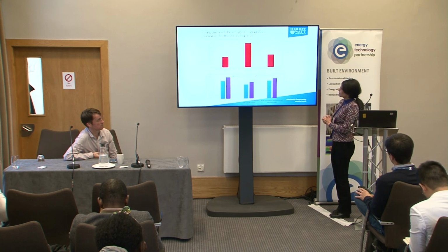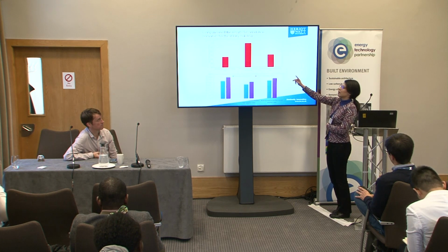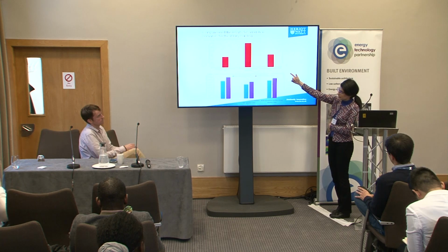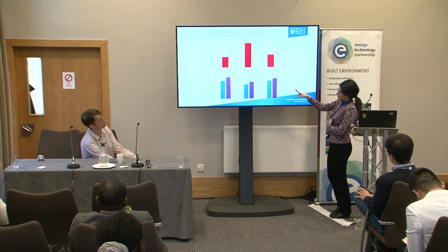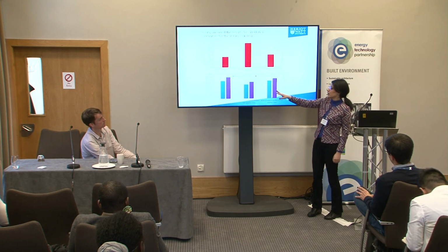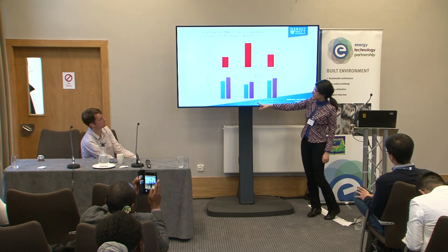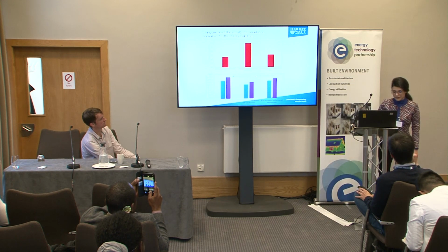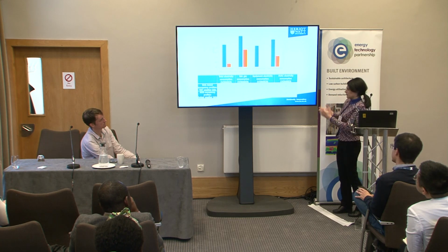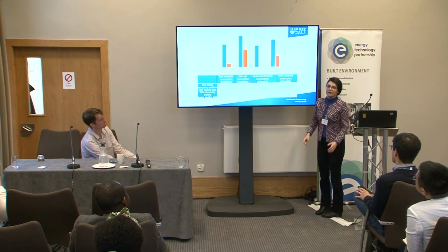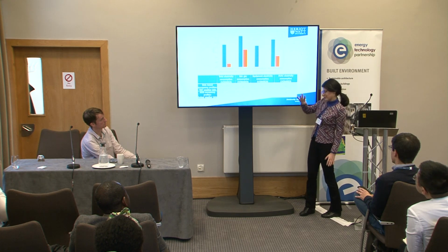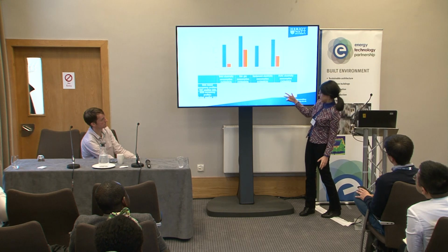For the library building, the natural gas consumption when we use actual occupancy profiles increases by quite a lot, but when we use actual weather data, it just increases a bit. The same goes for electrical equipment electricity consumption and HVAC electricity consumption, with the difference that actual occupancy profiles decrease the energy consumption. So if we compare the results using the metric for comparison, which is CVRMSE, we can see that using actual occupancy profiles has led to these differences, while using actual weather data has led to much smaller differences.